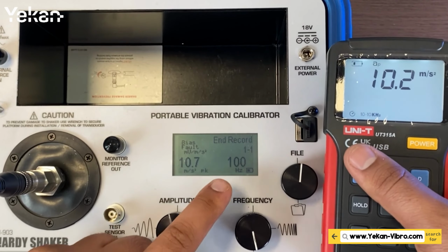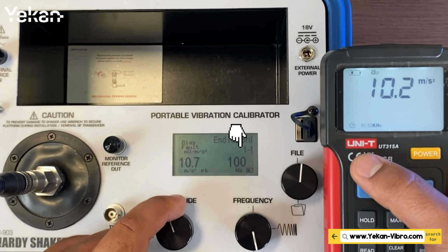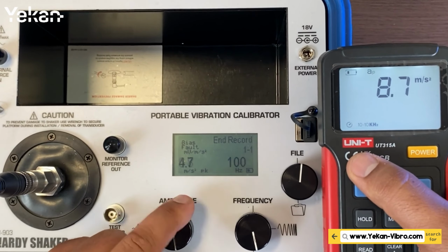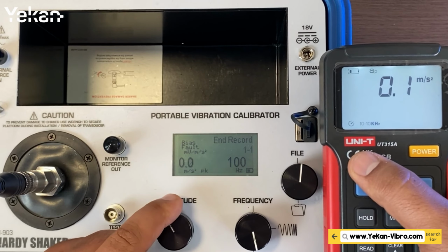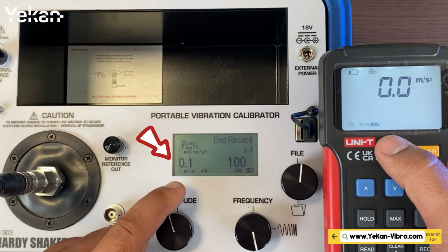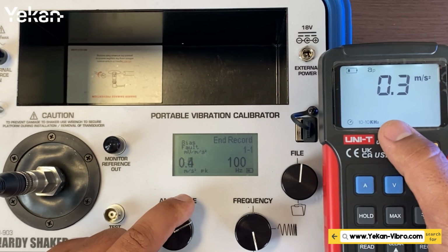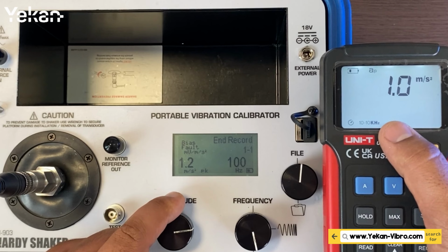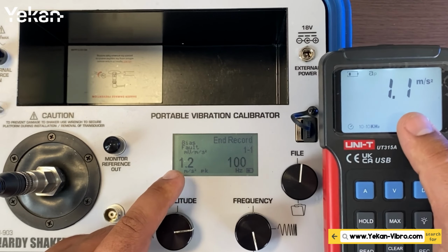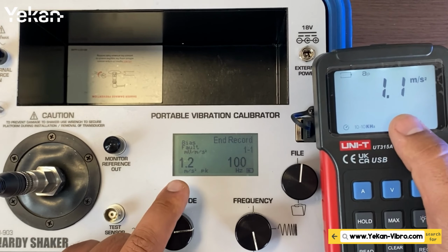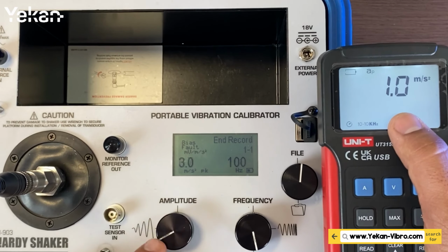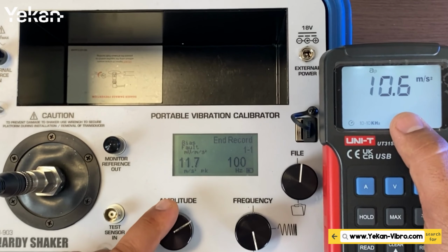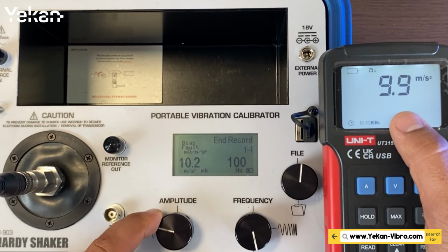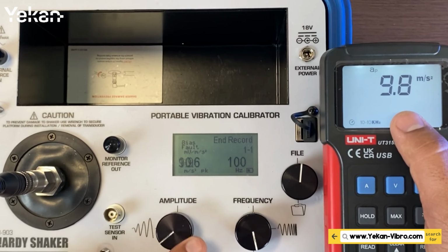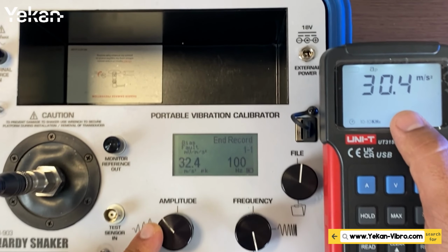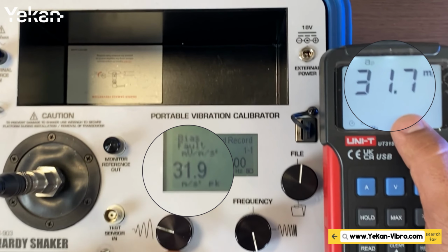In frequency test, we set frequency constant, like here at 100 Hz, and reduce amplitude. One of the challenging places for devices and sensors is at low amplitude. For example, at 0.1 here shows just 0. This issue is very challenging. And of course, my difference here and there is calculated and error percentage is obtained. In my opinion, the data it now shows is very good and acceptable data. We go to value 10. We go higher. More vibration. Becomes 32, you see it follows it.